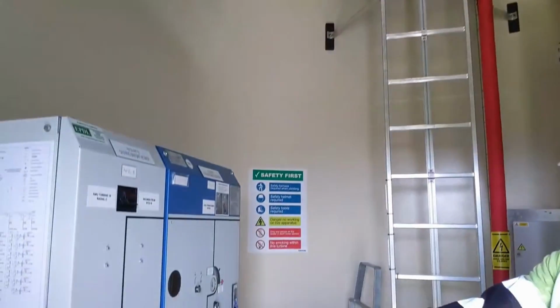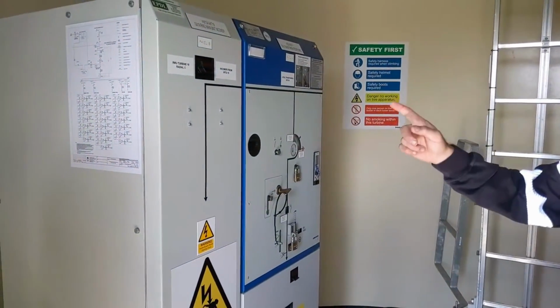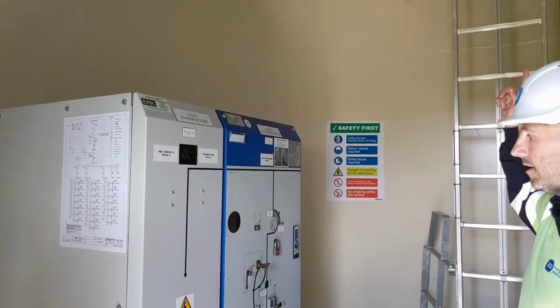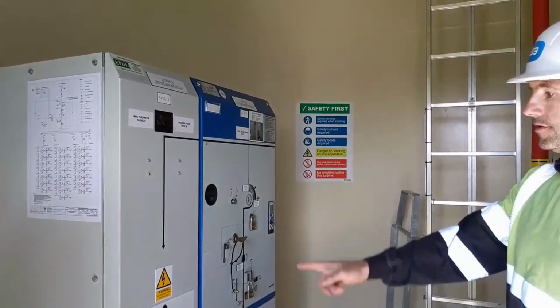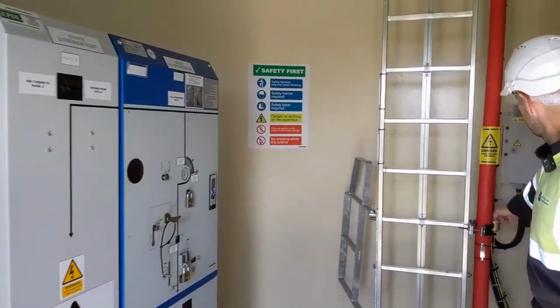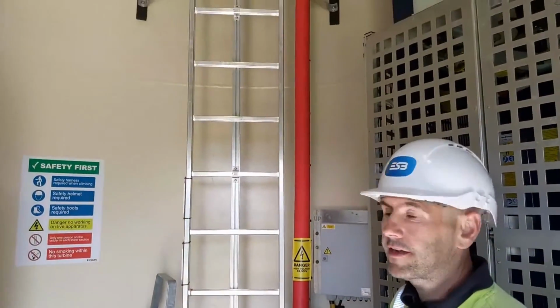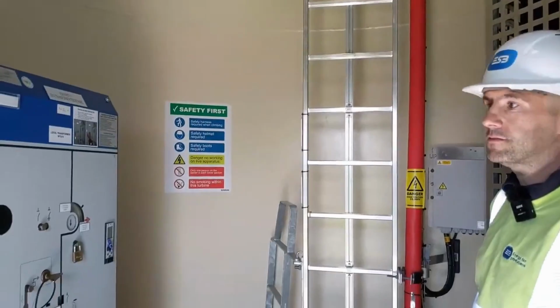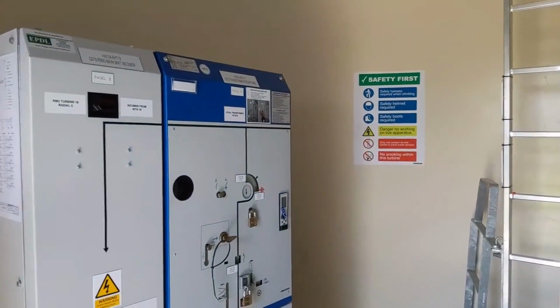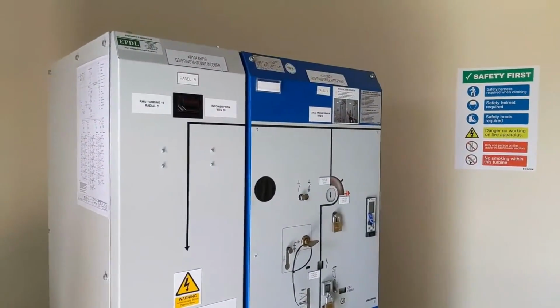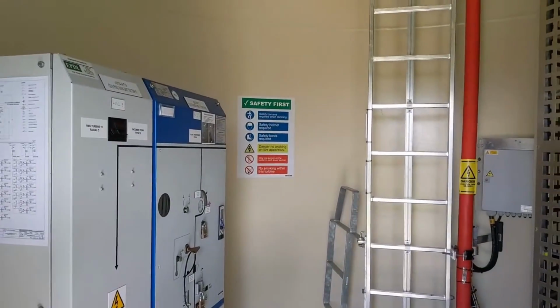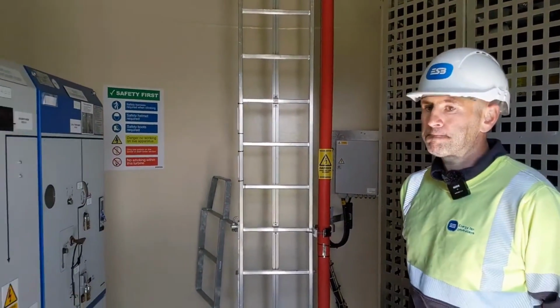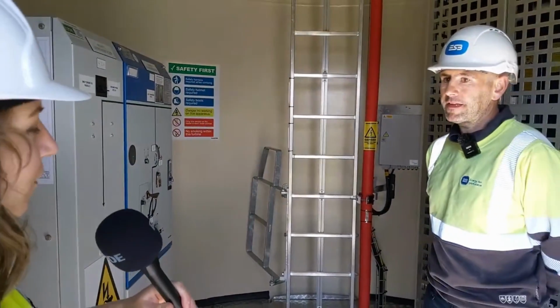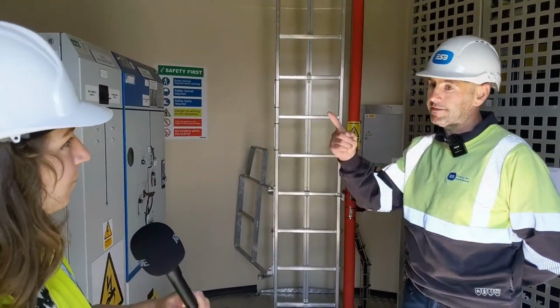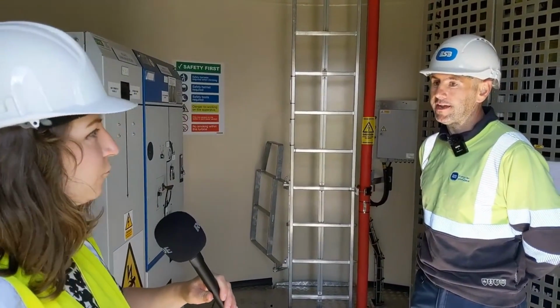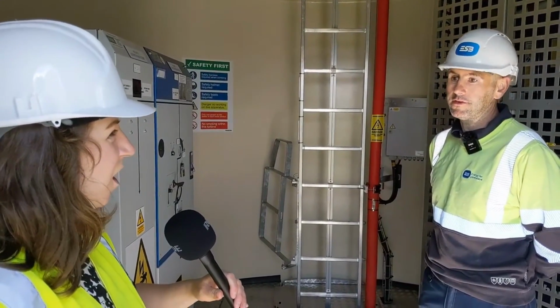Here we have the high voltage switchgear. This is what's providing the power to the nacelle. That comes in at 33,000 volts and then climbs up this cable, the red cable there, up to the transformer upstairs, where that gets turned down to 690 volt. The thing that I'm surprised about is how high voltage that is. So 33,000 volts, and that gets converted and sent off to the national grid. Is that right? That's right. But it gets stepped up down at the substation again, up to 132,000 volt onto the grid.